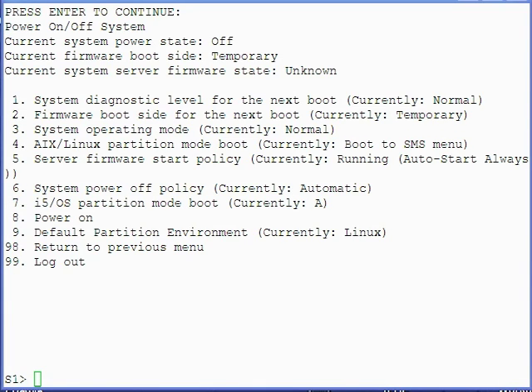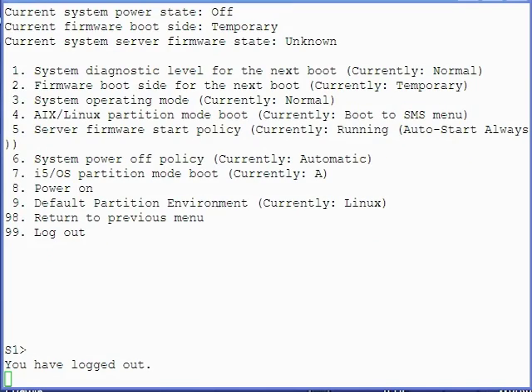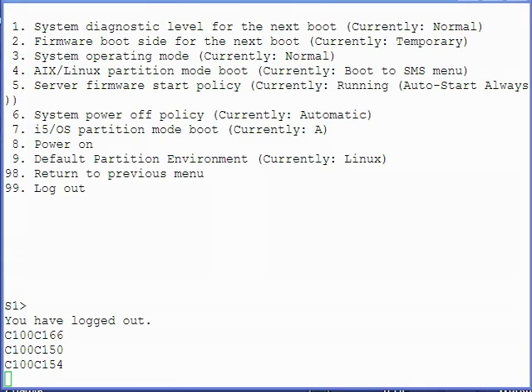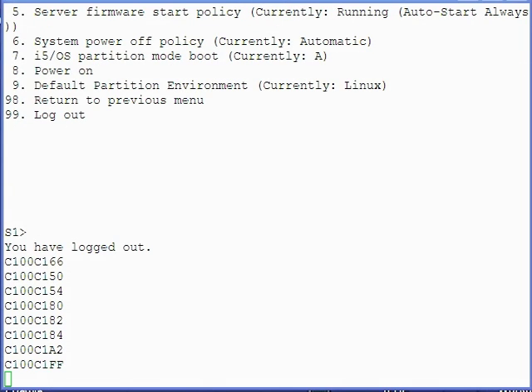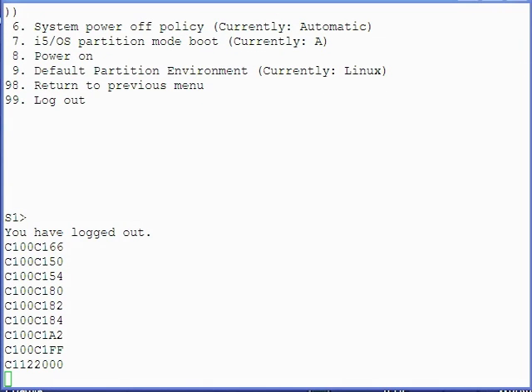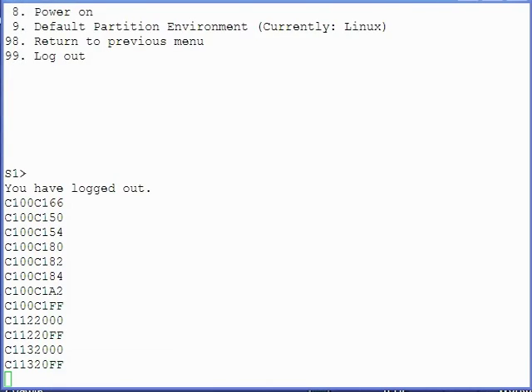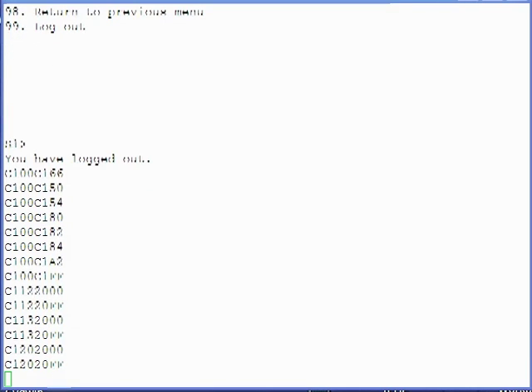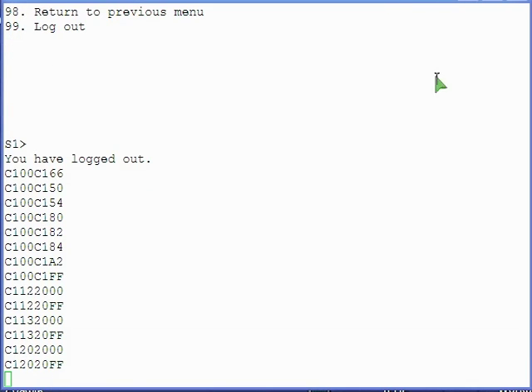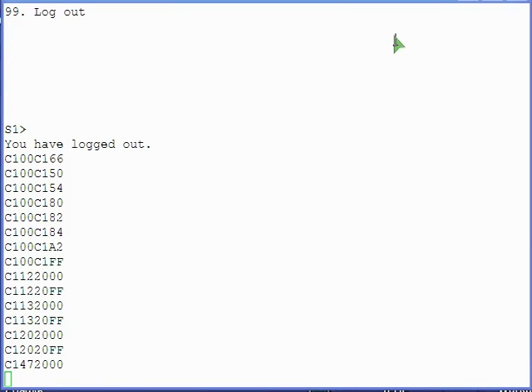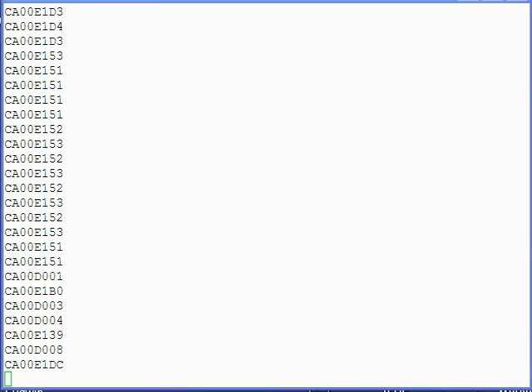After a few moments, you are automatically logged out of the FSP as the server is being powered on. Signs that the system is powering on include reference codes appearing in the console and on the control panel display, the sound of the cooling fans operating, and the green power LED on the control panel transitioning from flashing green to solid green.